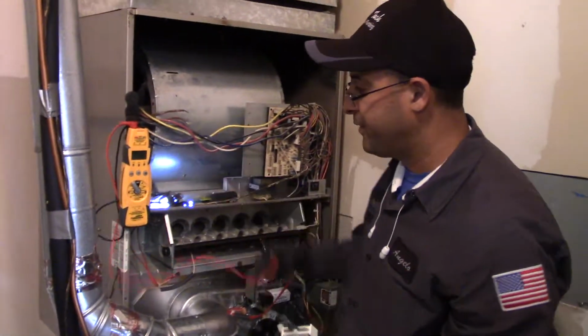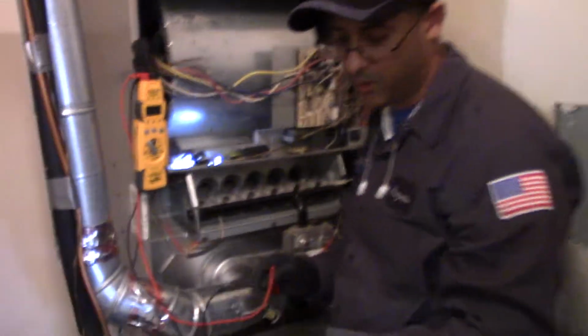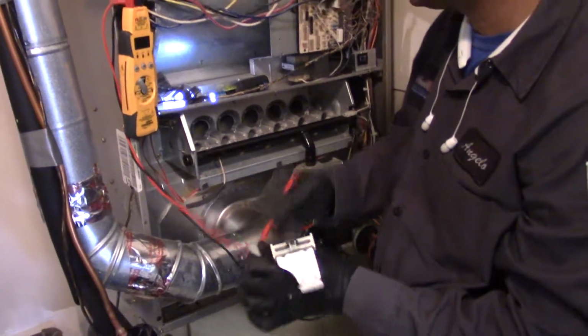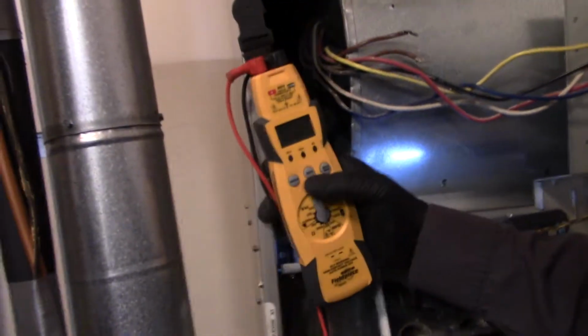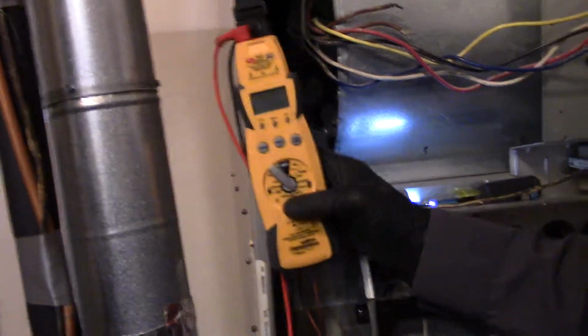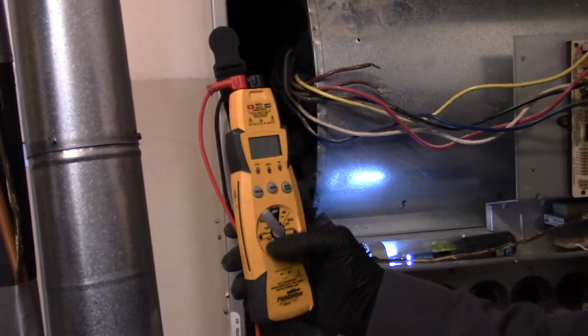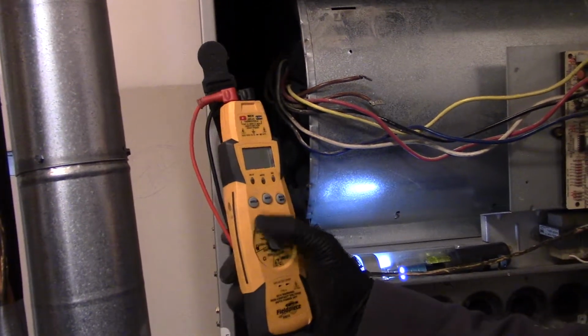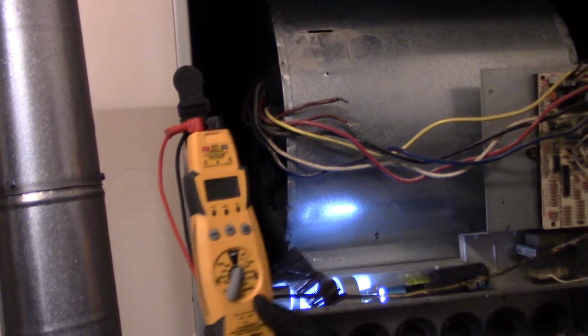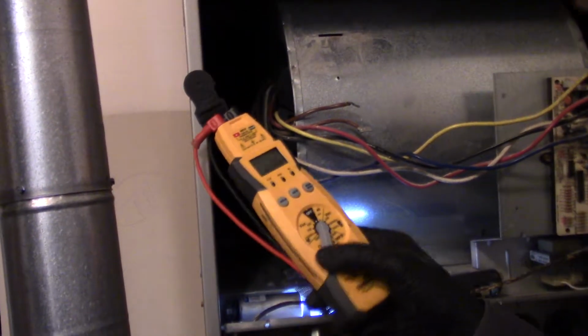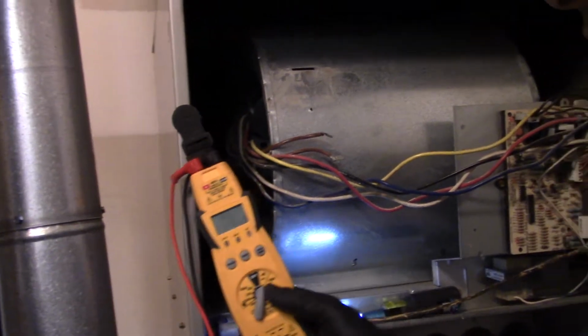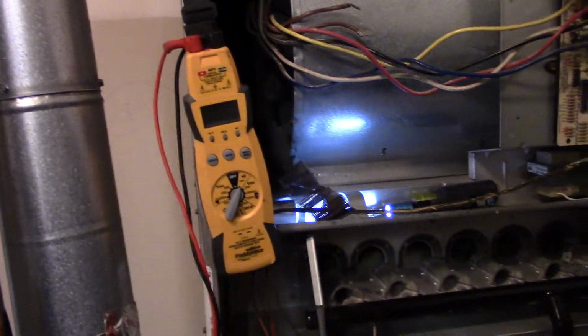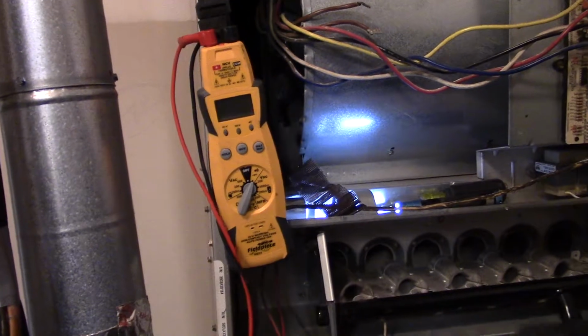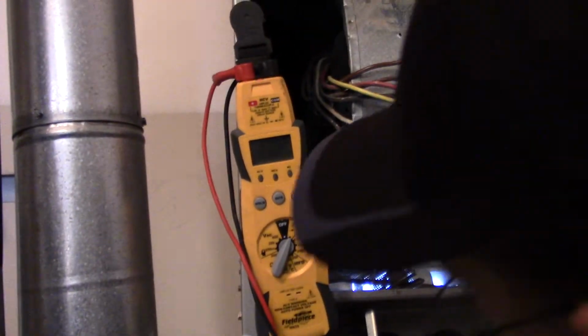I believe it's 50 to 71 ohms on these igniters -- again, I wrote that down in the book and we can verify that. On this one I'm going to set it to read resistance, since I like to use resistance, but my meter is dying here. See if it's hard to read that or see that right there. Yep, it's dying.